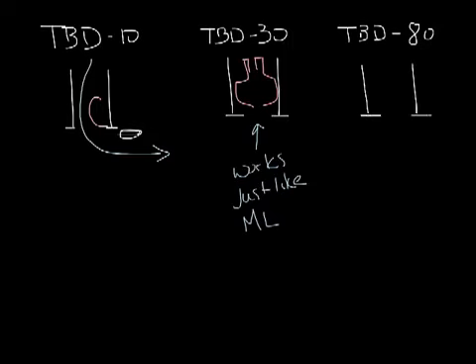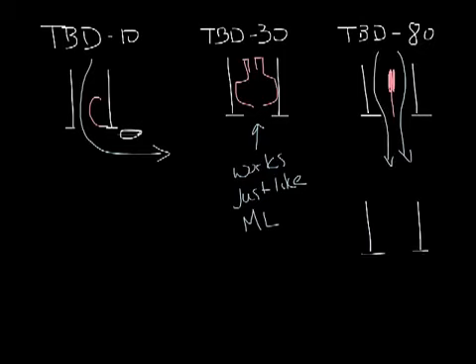In the TBD 80, the pattern controllers are kind of a flat blade with a gasket on it. So this little end is the gasket. So if it's set like this, the air is just going to come through and go straight down. Now if you take it and angle it to one side or the other, now you're going to create that low pressure zone. And the air is going to come in and hold to the ceiling like this.